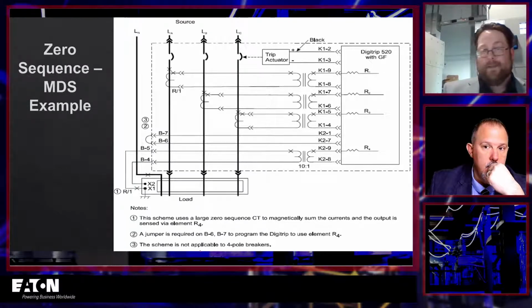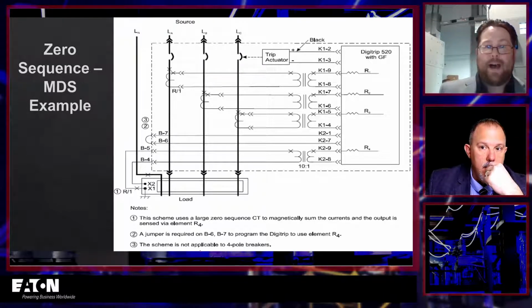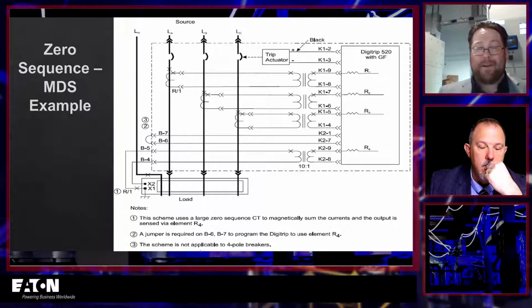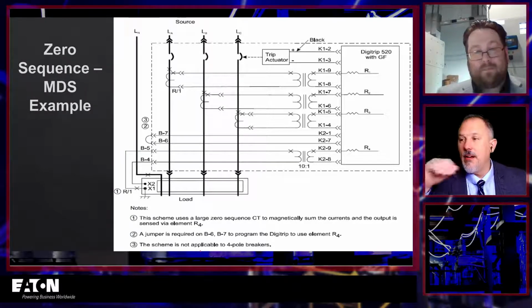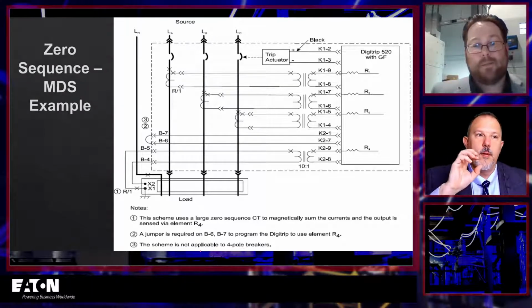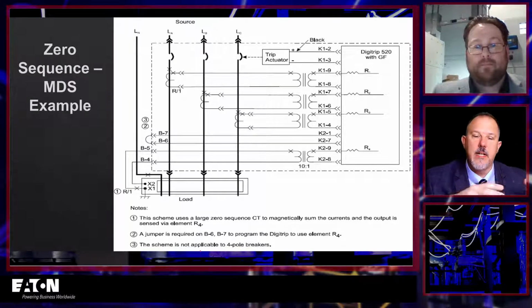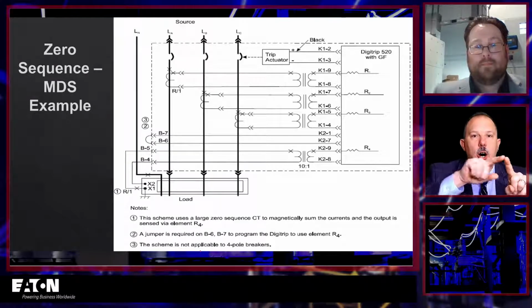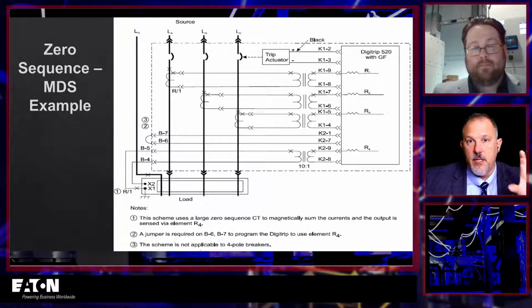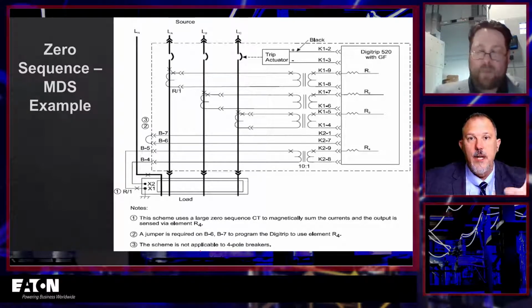Now, a little different here for those on the call that ultimately work in that utility world and the higher voltages. When you start talking about ground fault protection, you have to really be concerned about that saturation. And once you start working with relays, you have to be concerned about all the burdens that are going to occur. There's a lot of calculations that go into how you choose the right CT. Yeah. I've done burden calculations, which basically for a CT, you're looking at all of the different devices you have in that CT circuit, because it's only going to be able to handle so much load in that CT circuit.